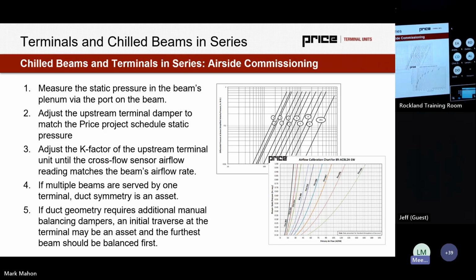Now, if we're looking at one terminal serving one beam, we would use the terminal damper as essentially the static pressure balancer for the system. So we would set the terminal's damper to meet the beam's design static pressure. Now the third step here, once we have the beam's pressure balanced correctly, is we would actually check the K factor of the upstream terminal, and we would adjust it to rectify the differences between the beam equation and the terminal K factor equation, which is going to account for ducted system effect, a lack of standard conditions. It's going to help to essentially make sure we're actually controlling to the intended max of the beam down to the intended minimum of the beam.